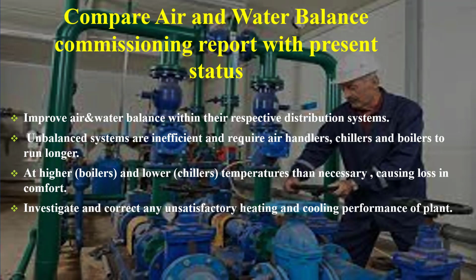Compare air and water balance commissioning report with present status. Improve air and water balance within their respective distribution systems. Unbalanced systems are inefficient and require air handlers, chillers, and boilers to run longer, at higher boiler and lower chiller temperatures than necessary, causing loss in comfort. Investigate and correct any unsatisfactory heating and cooling performance of the plant.